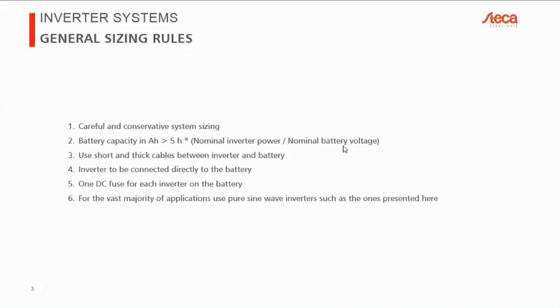Now, there is obviously a lot of pressure from customers to reduce battery sizes because, of course, the battery is the most expensive component typically in any PV system, in any off-grid PV system at least. So customers will pressure you to reduce the battery size. In that case, with some of our inverters, for example, the SOLARIX PLI, we give you a certain value as an absolute minimum. So for the case of the SOLARIX PLI, regardless of whether it's the 5 kilowatt or the 2.4 kilowatt version, because they work with different battery voltages, the minimum battery capacity is always 200 amp hours.